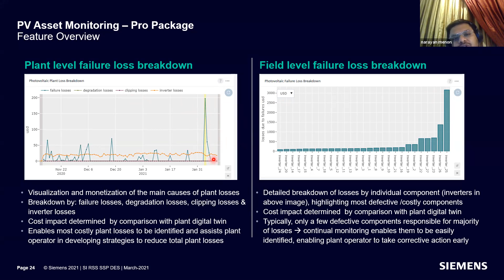A classic example: we installed a 1.8 megawatt PV plant in California with 25 inverters. Before installing DESMAC, problems showed up but people didn't realize the kind of impact it had on the facility. Once we installed DESMAC and started monitoring the system, we came to know exactly which inverter was not performing. Through heat maps and graphs, we found that inverter 25 was completely malperforming - not performing at all.